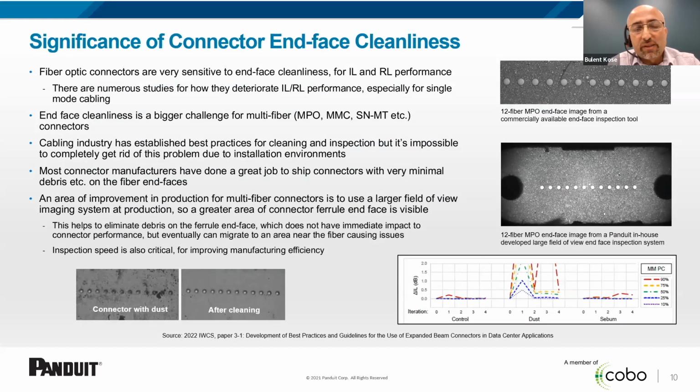Now I wanted to talk about some of the installation issues for multi-fiber, high-density connectors, starting with the end-face cleanliness problem. Fiber optic connectors are very sensitive to end-face cleanliness, obviously, which causes insertion loss, return loss, and performance issues. Especially for single mode fibers, this is even worse, and it is a bigger problem for multi-fiber connectors.